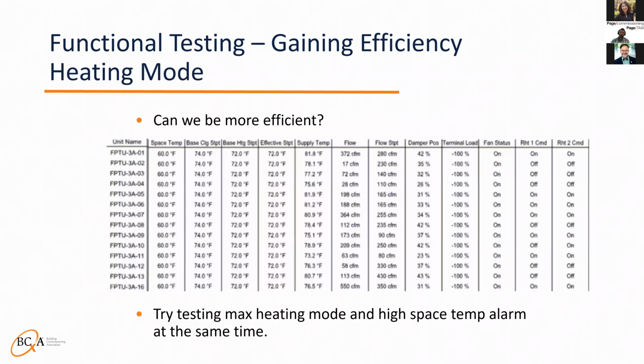Heating mode. When we test the other extreme, all high alarms will be tripped at the same time, and you can quickly click through the sample of boxes to verify the alarms appear on the graphics. So believe it or not, this is an image of a settled system. Obviously, there were a lot of issues. This one happened to have an overactive PID loop on top of that.